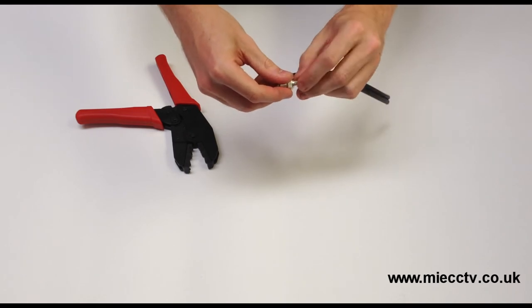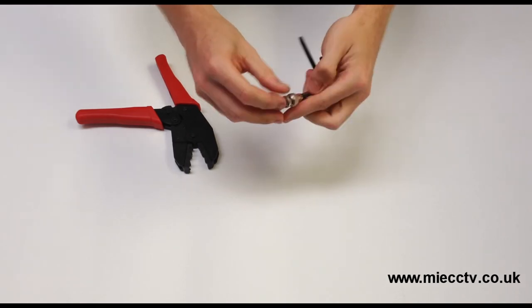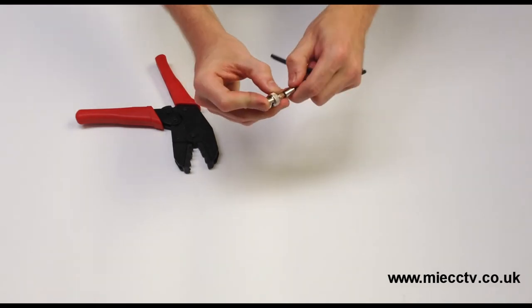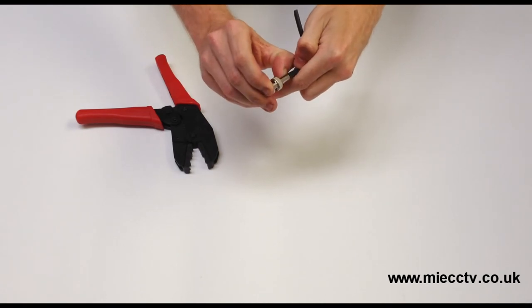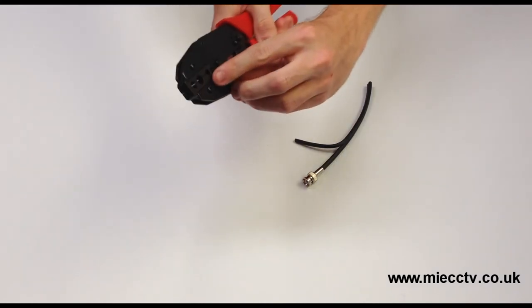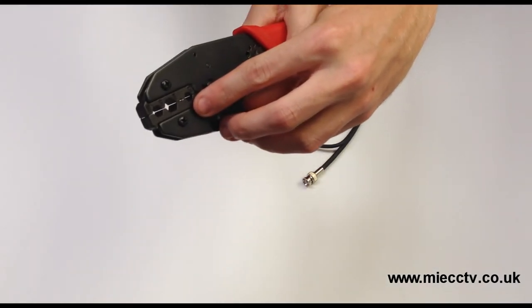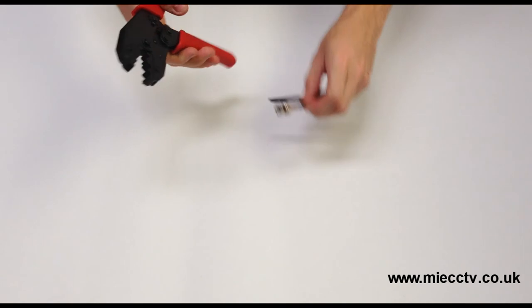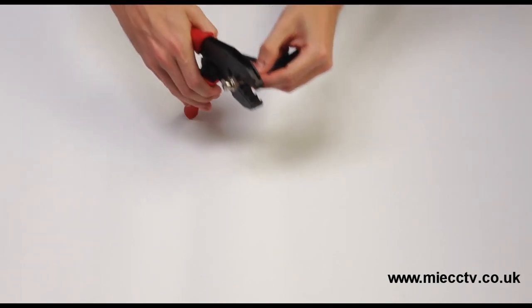Now you can crimp the ferrule, this requires a 0.256 inch or 0.255 inch crimp. Place the ferrule into the jaws of the crimp tool and once again close the tool until the ratchet releases the cable.